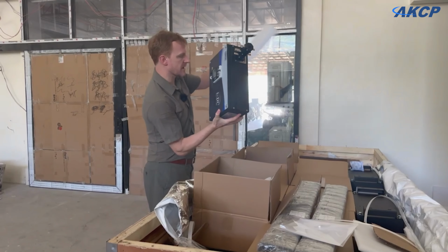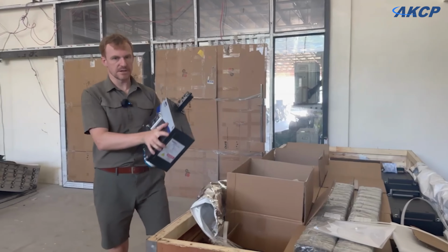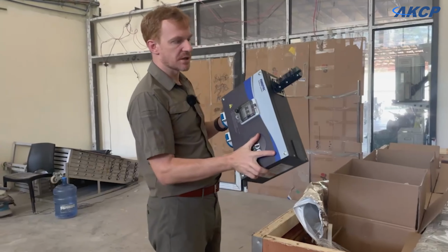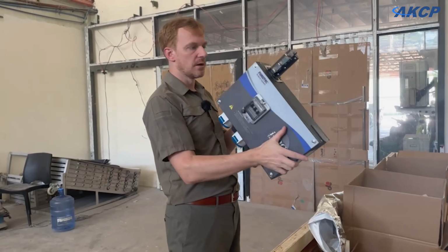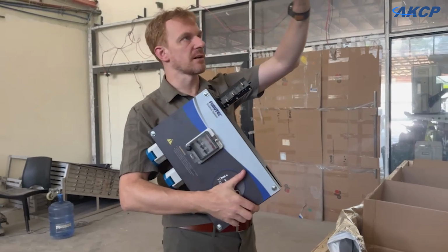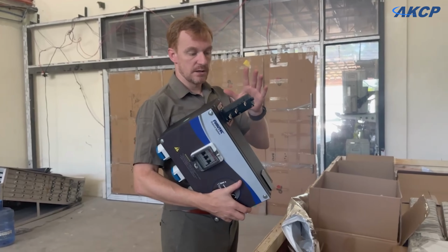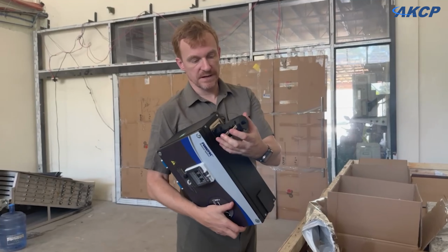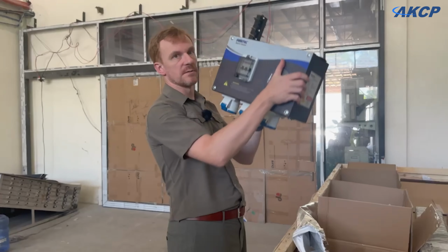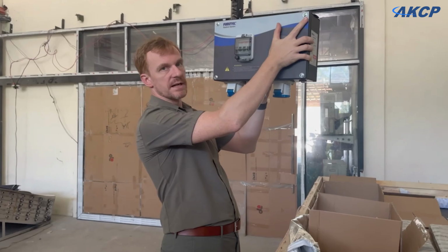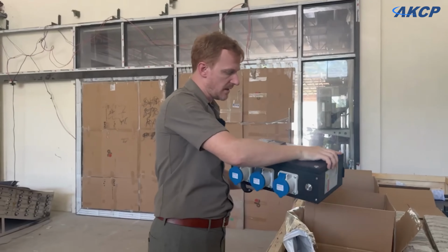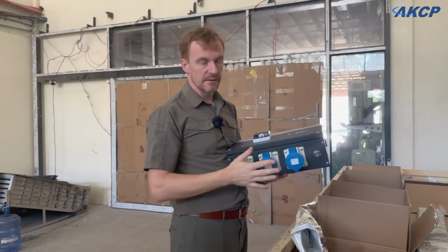This is one of the breakout boxes that inserts into the bus bar, which runs above the racks. The bus bar is an extruded aluminum channel that carries the power, with a three-phase connection. This slots into the bus bar and stays in place above each rack. It's got a built-in breaker and 3 outlets.